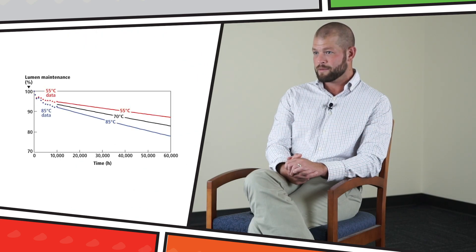If your environment is hot, make sure the high bay you choose shows a chart of lumen maintenance versus temperature, and that this performance works for you. Remember that lumen maintenance performance drops significantly at temps above 77 degrees Fahrenheit.